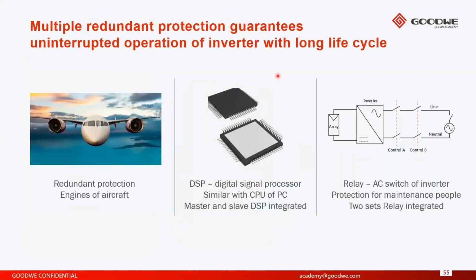In terms of the design of the inverter internally, we have redundant components such as master-slave DSPs. So, for example, if there is a problem with a master chip, the slave chip can take over the functions of the master until the master has been able to reboot itself and then come back online. And we also have multiple AC relays on the output to allow a much higher level of protection in terms of anti-islanding.